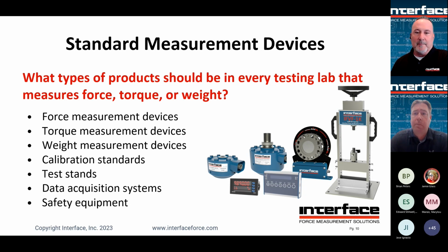So force measurement devices would be load cells, different types of load cells, whether you're doing tension and compression testing, perhaps compression only, or even getting into a multi-axis for additional measurements that need to be taken. Torque measurements could consist of torque standards, torque wrenches, torque verifiers, even lever arms if you're performing some types of low-level torque testing. Weights and measures would also be things like calibrated, certified dead weights that you may use to perform, again, low force or low torque range measurements and calibrations.